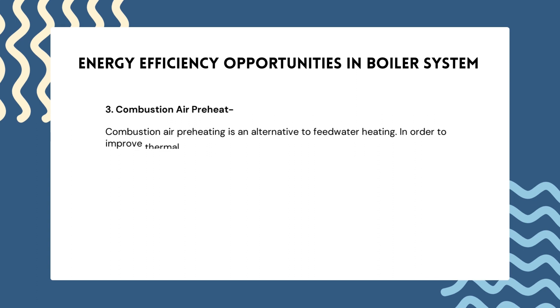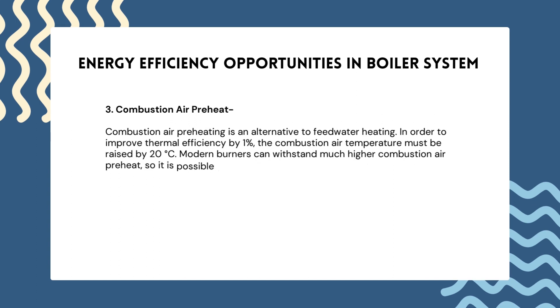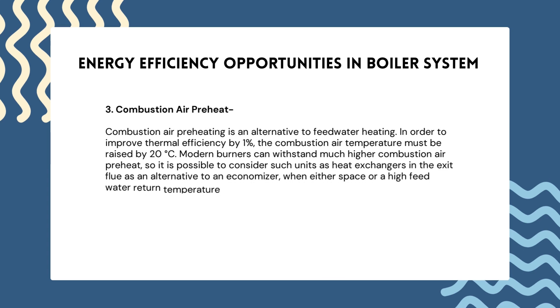For a modern 3-pass shell boiler firing natural gas with a flue gas exit temperature of 140°C, a condensing economizer could be used. Third, combustion air preheat: combustion air preheating is an alternative to feed water heating. To improve thermal efficiency by 1 percent, the combustion air temperature must be raised by 20°C. Most gas and oil burners in boiler plants are not designed for high air preheat temperatures, though modern burners can withstand much higher combustion air preheat.